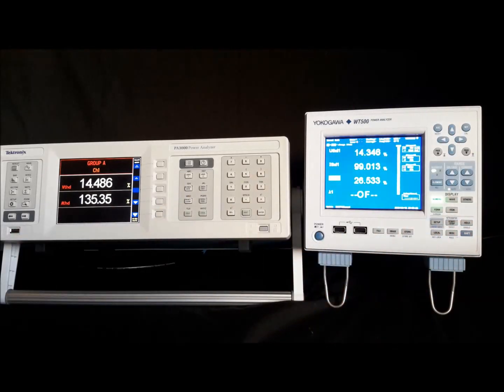Okay, so the voltage harmonics, as I said before with the bar, I'm not particularly concerned about, and you can see from the percentage mark here they're pretty much the same. The current harmonics though is very different, with the Yokogawa being stable around 99.9 total harmonic distortion, whereas the Tektronix for some reason seems to be going a little bit loopy, and this is at 100 kilohertz, so a tenth of the advertised range. It's showing harmonic measurements up to 1000%, which is a first. So I think what I'm going to have to do now is to start looking into specs and start looking into calibration. So let's load that up and see what we can see.